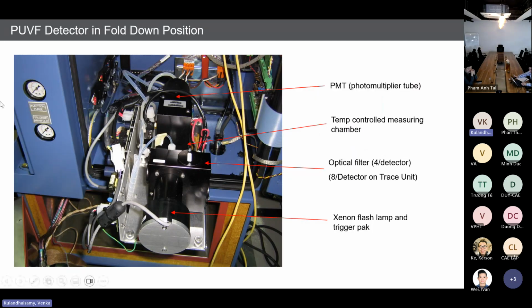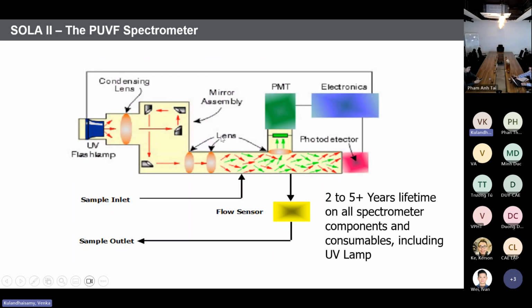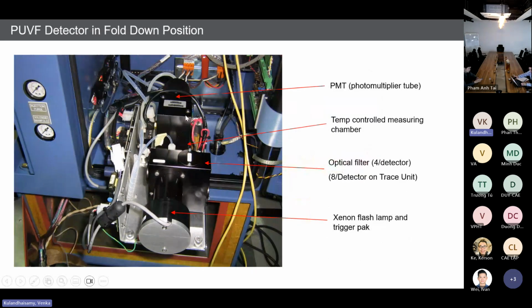Yeah. So inside the electronic chamber, you can see this is the PUVF bench. Here is just a line diagram. Here you can see physically how the PMT bench, that means the PUVF detector, looks like. So here is a PMT tube. This is the temperature controlled measuring chamber, then optical filters, then the UV lamp fitted with the trigger pack. The trigger pack will trigger the UV lamp at 10 flickerings per second.